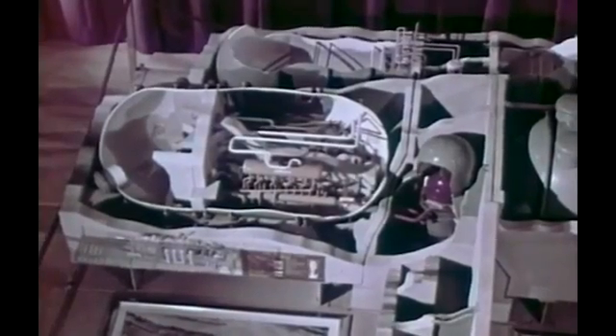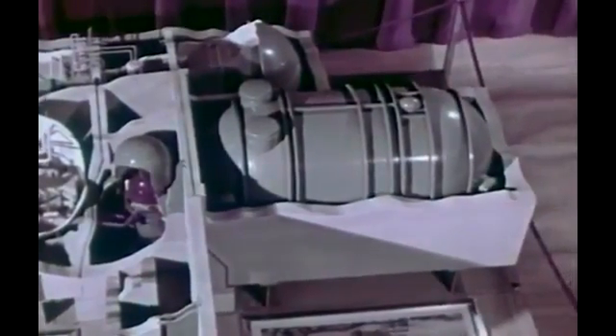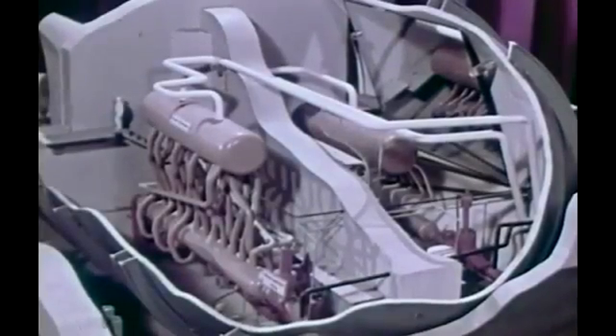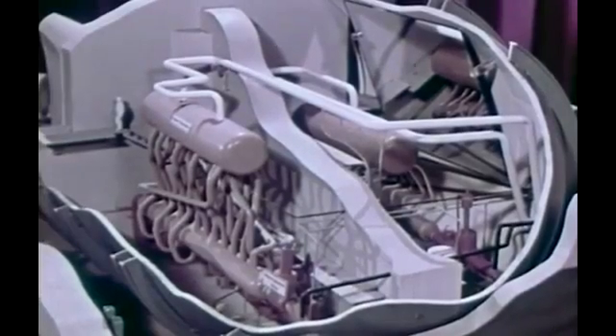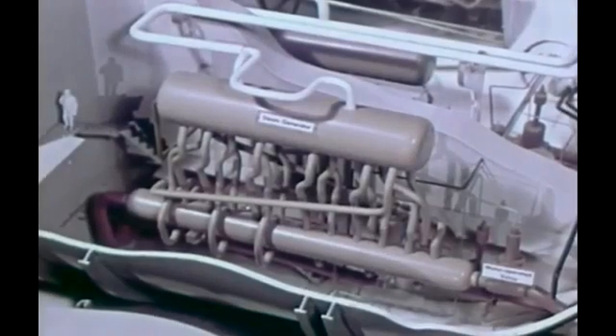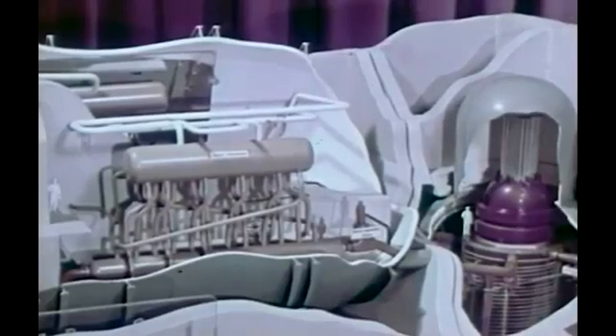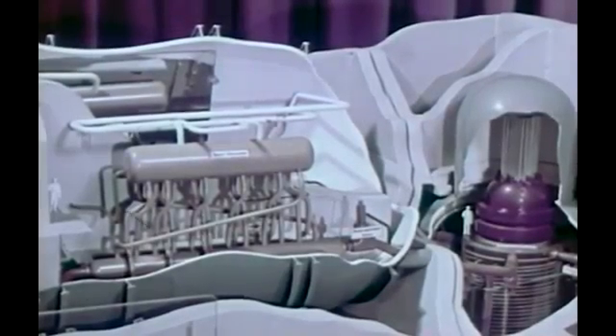Three underground chambers, steel shells 50 feet in diameter and 1.25 inches thick, along with the sphere containing the reactor, make up the plant container. This is one of the 2 similar boiler chambers. A concrete shield separates the 2 loops within it, permitting access to an inactive loop while the plant is operating. The steam generator consists of this steam separator and heat exchanger. The 4 loops are capable of producing a total of over 1 million pounds of steam per hour.